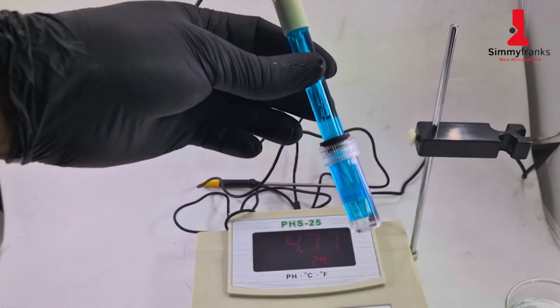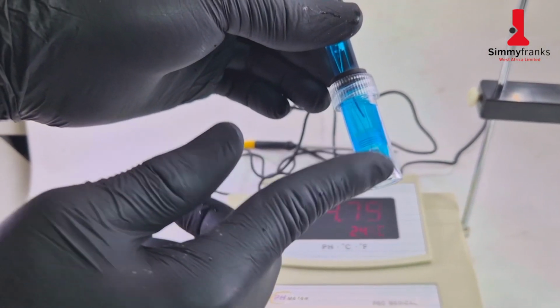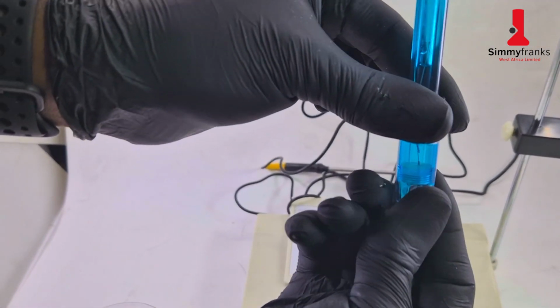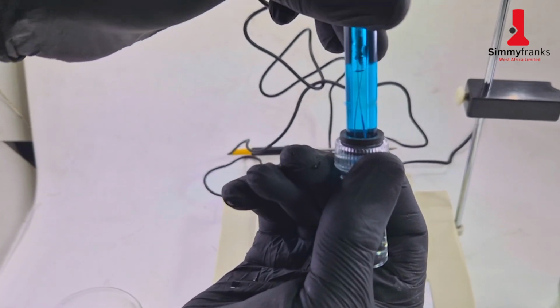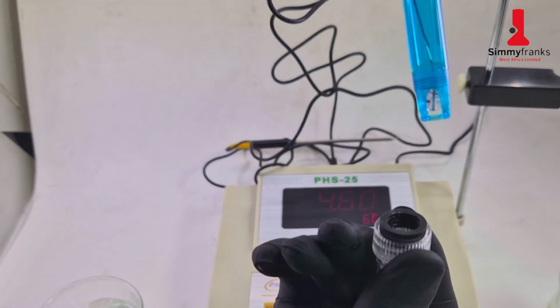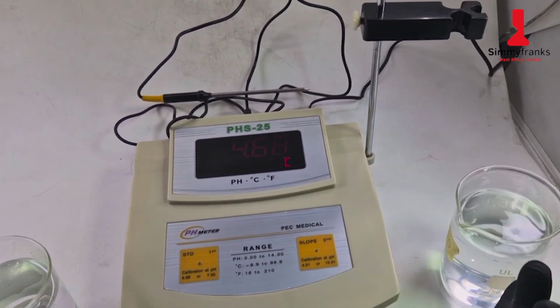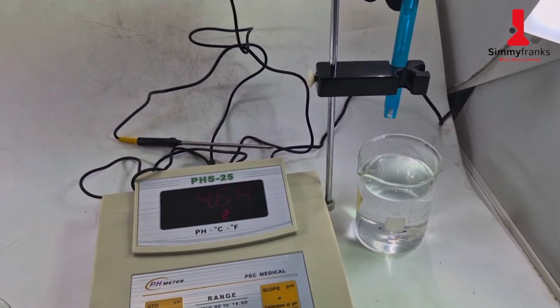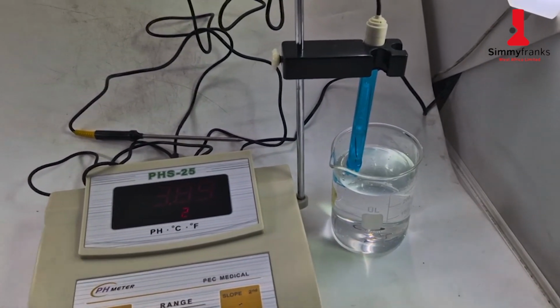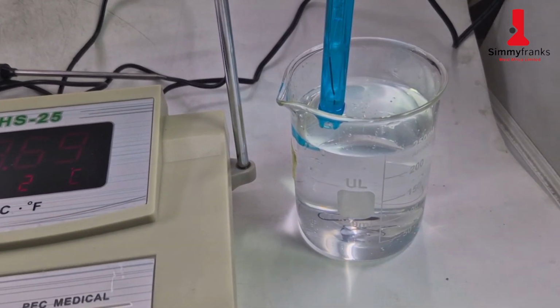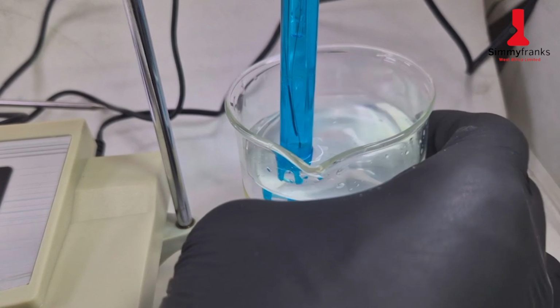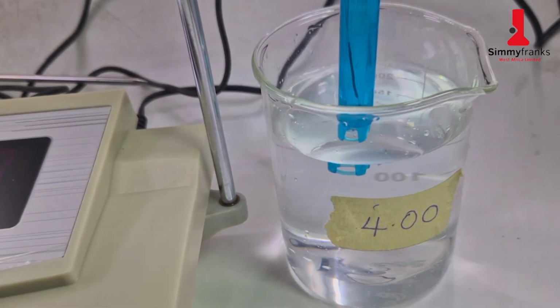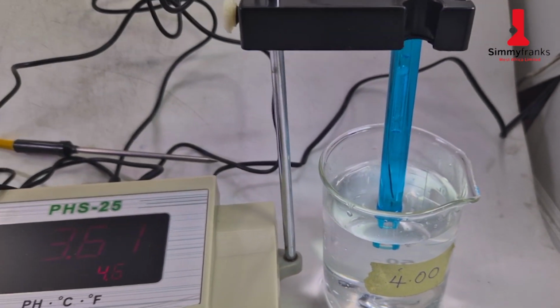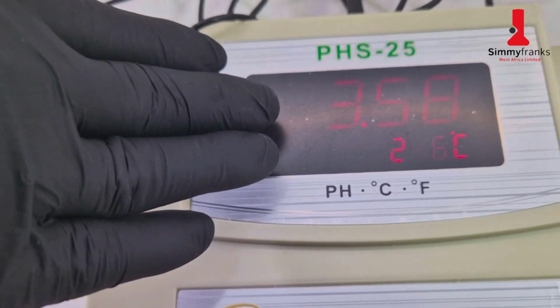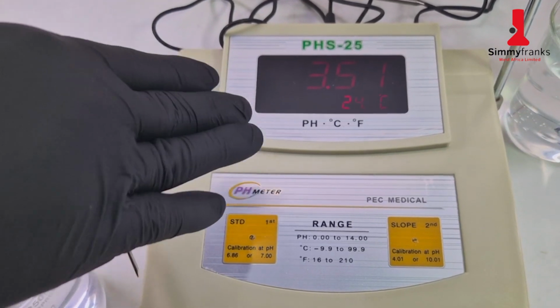Now I'm going to remove my probe from the storage solution. So there's a solution in it. So I'm going to take out this probe first. I'm going to open the container for the storage probe solution and then gently pull the probe. Now the probe is out of the storage solution. So with my liquid in place, I'm just going to put my pH probe in the water. So this is still the 4.0 liquid. And then once you do that and look at your screen, it's yet to stabilize, so we'll wait for it to stabilize. So at the moment it's at 3.51. So there is where it's stabilized.